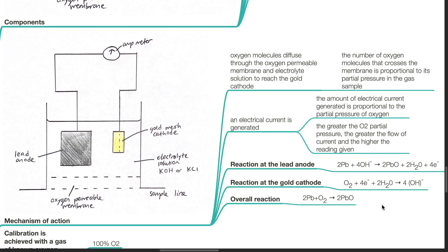Mechanism of action of the fuel cell: oxygen molecules diffuse through the oxygen-permeable membrane and electrolyte solution to reach the gold cathode. The number of oxygen molecules that cross the membrane is proportional to its partial pressure in the gas sample. An electrical current is generated, and the amount of electrical current generated is proportional to the partial pressure of oxygen. The greater the oxygen partial pressure, the greater the flow of current and the greater the reading given.